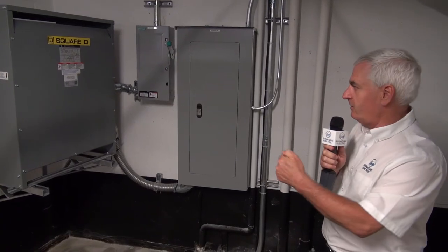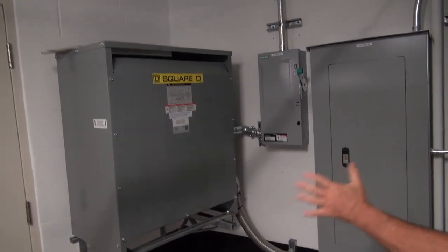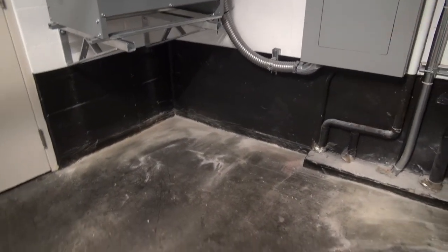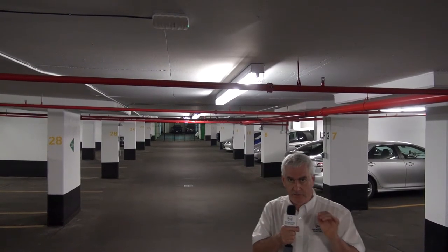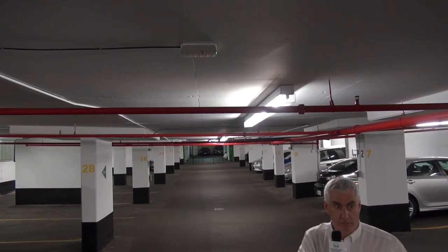This is one of the other panels at the site. There's an electrical room on this side and one on that side, but inside they're very congested, so we came out here and found just enough space. We need a meter clearance in front of the panel, and we got it up off the ground so that power washing won't damage anything. Keeping it close to the electrical room keeps the cost down. These are networked chargers, which means they need internet communication — either Wi-Fi or GSM cellular. In this case, they use Wi-Fi, and these antennas are hardwired throughout the garage as part of the original infrastructure.